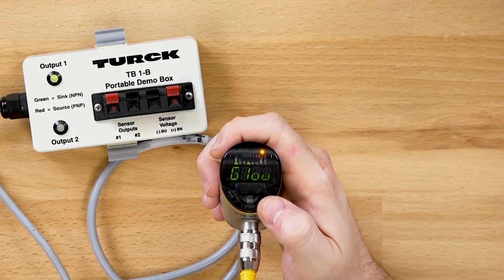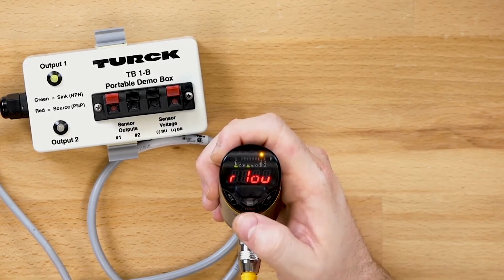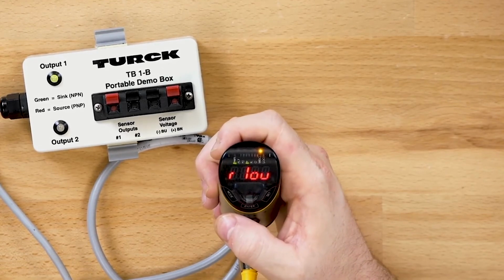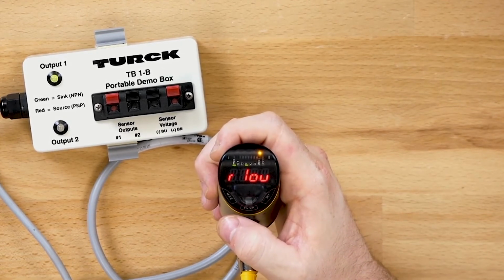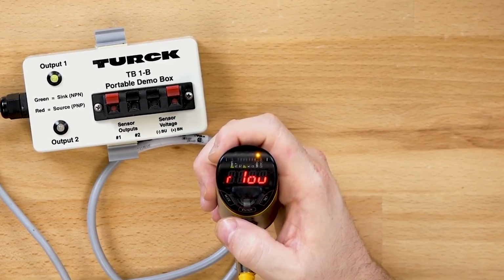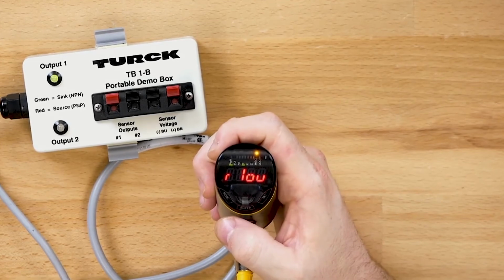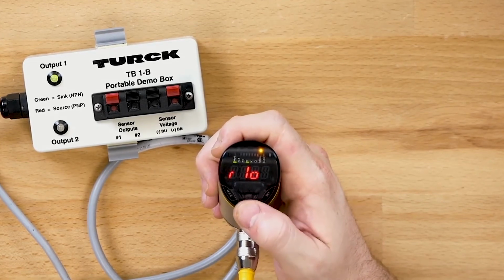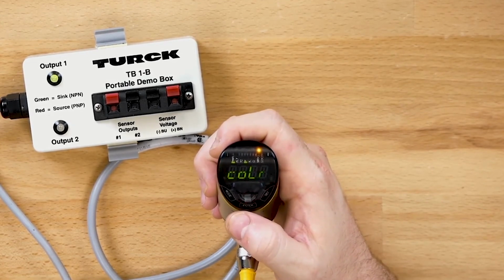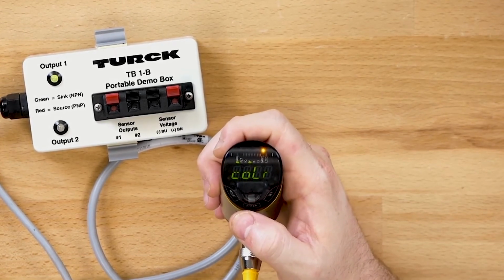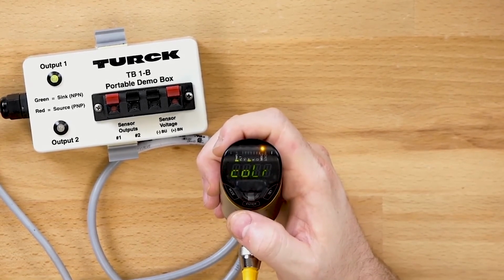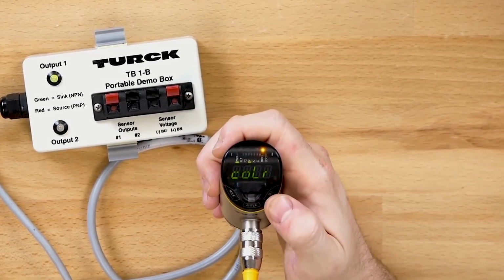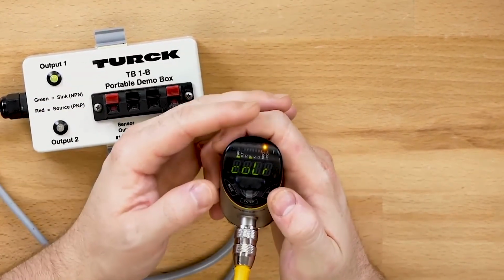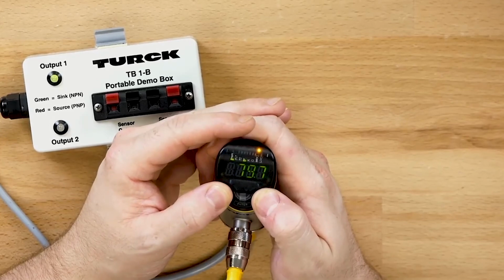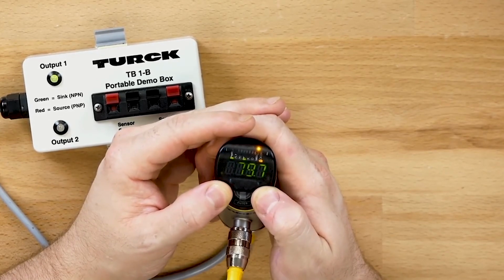We are going to look for the R1OU display. What this does is change the color of the display for the sensor to read red when the output is not engaged. Pressing Enter stores this parameter. We have the sensor programmed. To lock the sensor and revert back to the display screen, hold the Mode and Set touchpads simultaneously for 4 seconds. Note that the TS Plus also will lock after 60 seconds of inactivity.